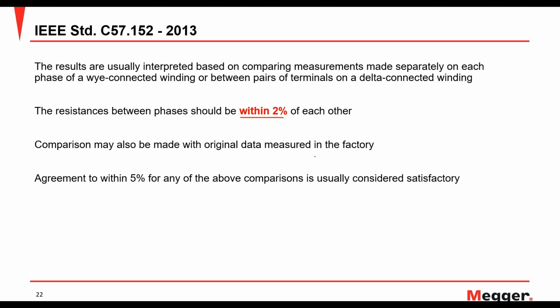Whenever you get a transformer from the factory, you get some test reports. What were the tests that were conducted when it originally left the factory? So you can also compare it to that data. Agreement to within 5% of any of the above comparisons is usually considered satisfactory. So if you're comparing to the original data or any other comparisons, within 5% is what you're looking for, and that's your pass or fail criteria basically.